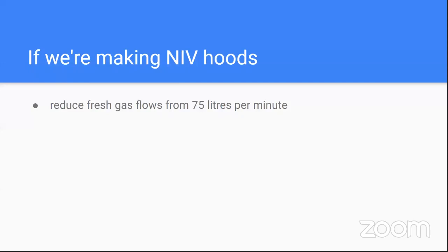Just to put this in perspective, humans typically consume about 200 millilitres per minute. So if you're connecting someone to a device where you're requiring 75 litres, you're wasting a tremendous amount of oxygen. So whether we redesign these with some valves so they don't rebreathe, or use some soda lime to scrub the carbon dioxide out so that you can reduce the fresh gas flow, there are some opportunities to optimise this, and that would be critical if these things are going to be deployed in the third world.